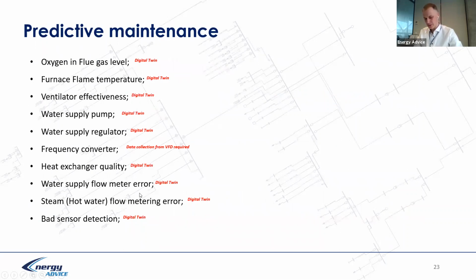For predictive maintenance, we can separate a boiler into the separate components which make an impact on the boiler operation. For example, the oxygen level of the flue gas. You remember, if the oxygen measurement is bad, we have either CO emission or surplus oxygen, and maybe better burning, but with losses. Furnace flame temperature: do we know this is the right temperature, what we see through a metering device? It's an interesting question, and probably not always is the temperature we measure the right temperature, what is exactly in the furnace.